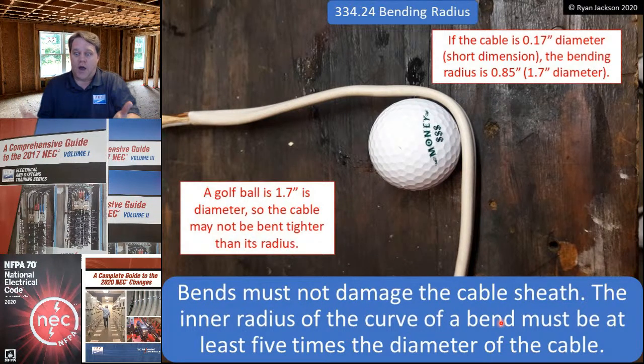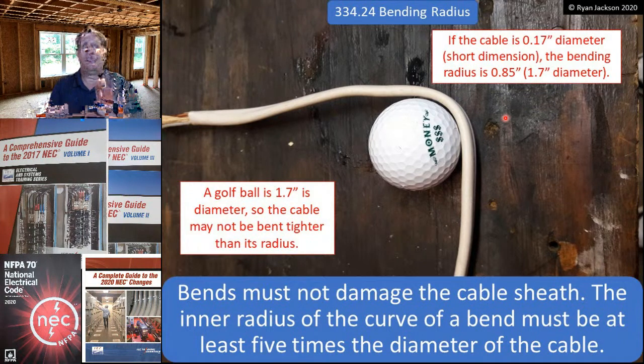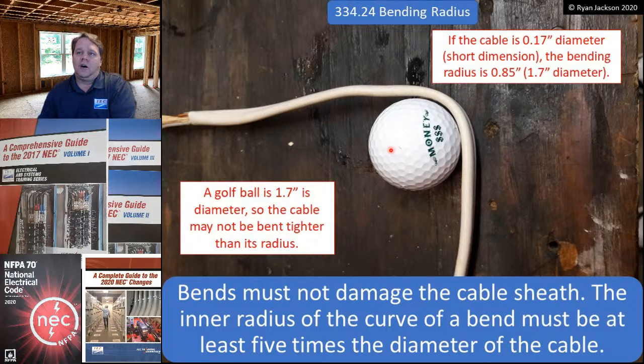So here's the deal. The bending radius for 14.2 or 12.2 is 1.7. And the 1.7 diameter, radius of 0.85, radius is half the diameter, right? So the diameter is 1.7. A golf ball is 1.7. This complies. You cannot bend NM cable tighter than you could around a golf ball. Does that make sense? So this complies. Any tighter would be a violation. And really, think about that. That's pretty tough to violate, in all honesty.